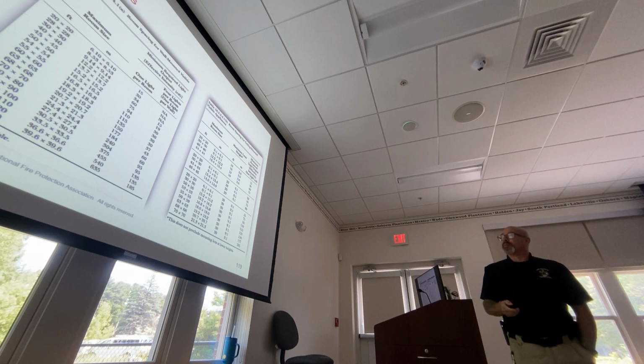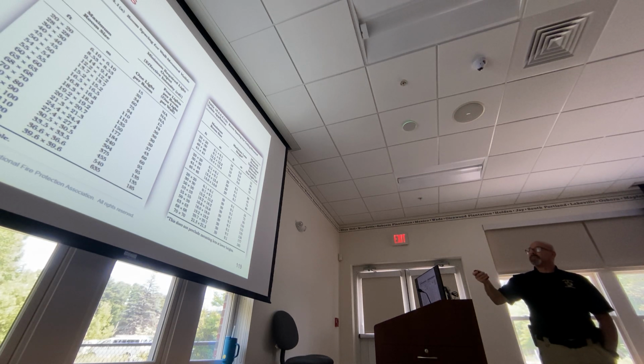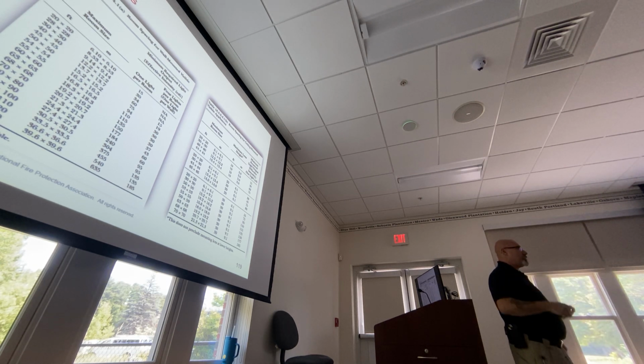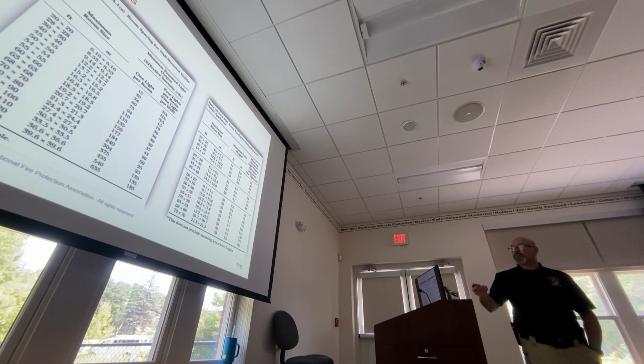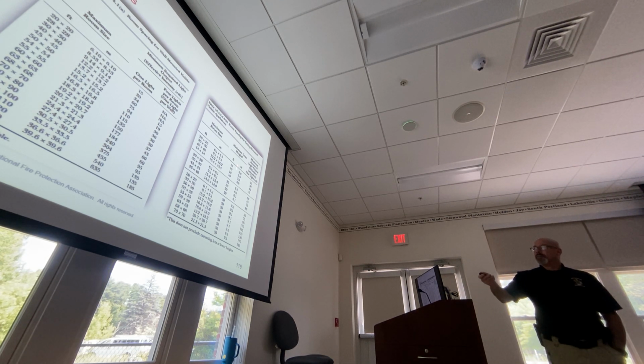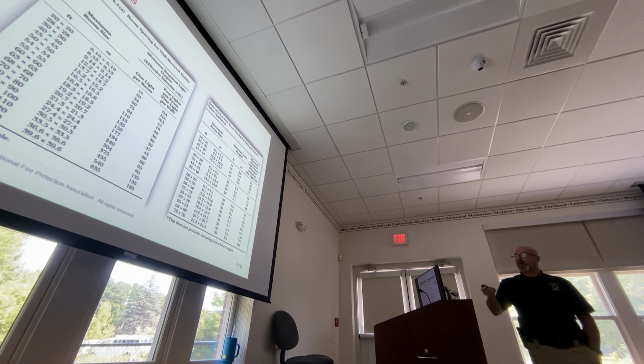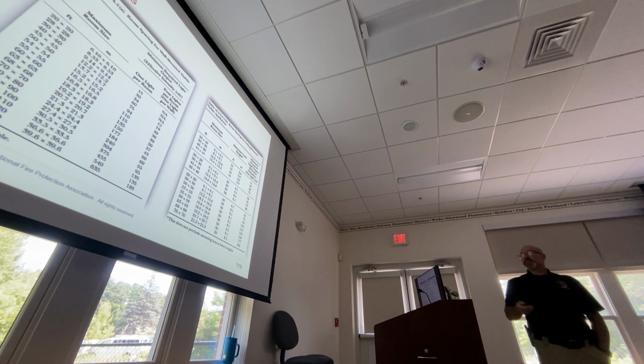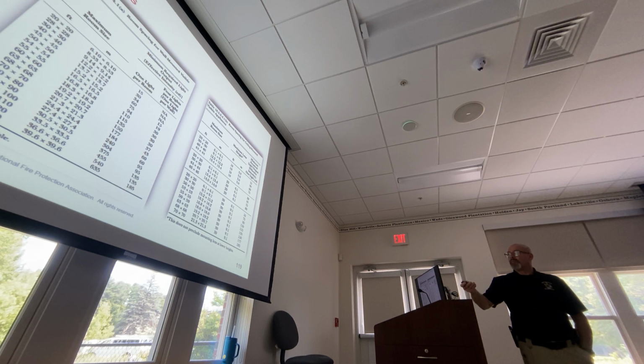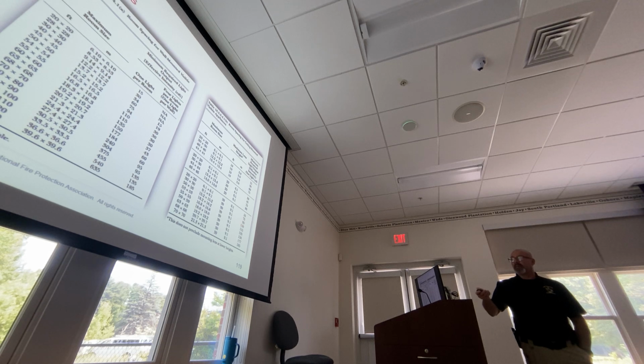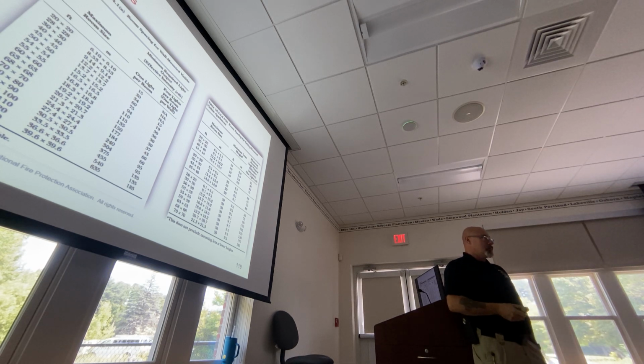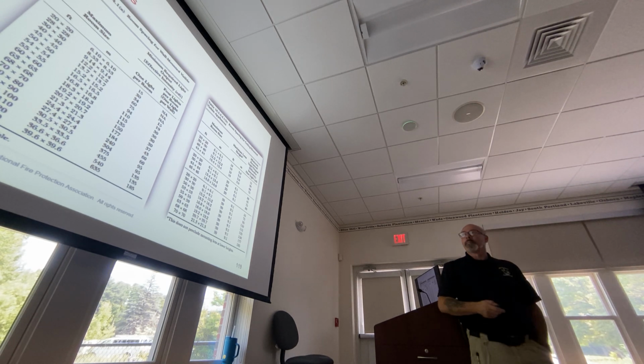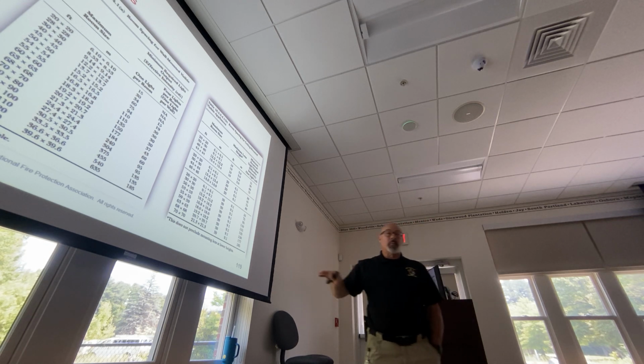Room spacing for ceiling mounted, that's for wall mounted. If we had a ceiling mounted in this, let's just say it's a 50 by 50 room, the maximum height of the lens, so where that light is mounted, can't be any greater than 30 feet high. Okay, so 30 feet or less. And my light output has to be at least 95 candela for that one single light in this 50 by 50 room, if it's on the ceiling. Does that make sense?